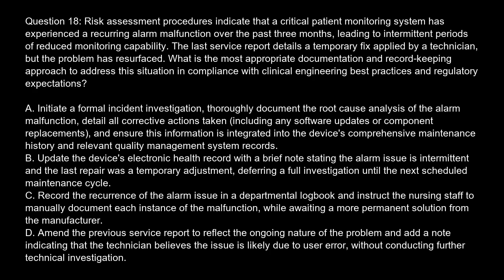Option A. Initiate a formal incident investigation. Thoroughly document the root cause analysis of the alarm malfunction. Detail all corrective actions taken, including any software updates or component replacements, and ensure this information is integrated into the device's comprehensive maintenance history and relevant quality management system records.